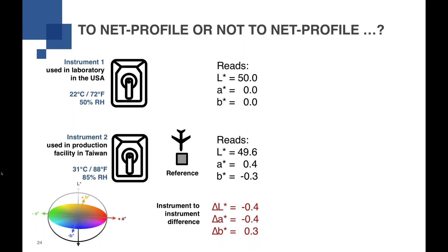So here we have an instrument to instrument difference, not necessarily caused by the instrument itself, but by the fact that we have different environments here of minus 0.4 in lightness, minus 0.4 in A, and let's say plus 0.3 in delta B. And depending on what kind of tolerances you want to achieve or maintain, that might be a big issue for you already. So the point is, Net Profiler helps you to compensate for these environmental differences so that you would actually get closer readings between two net profiled instruments, regardless of the environment. And that for us is the door opener for digital color management.